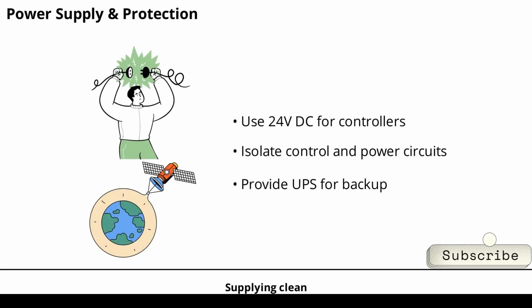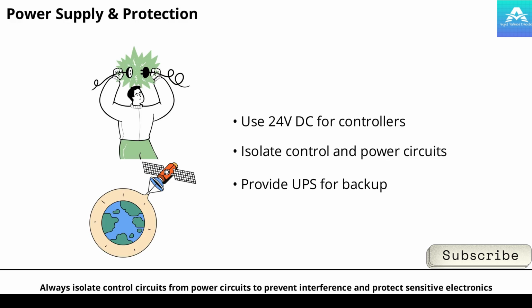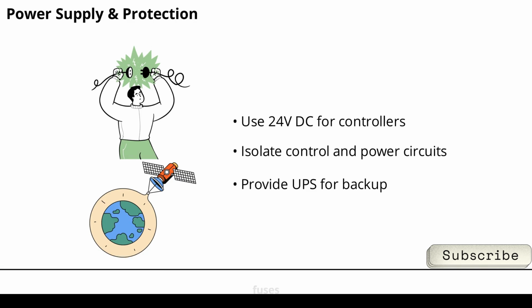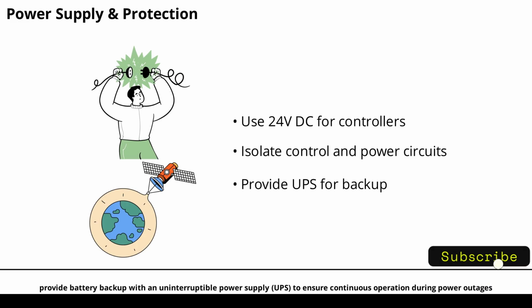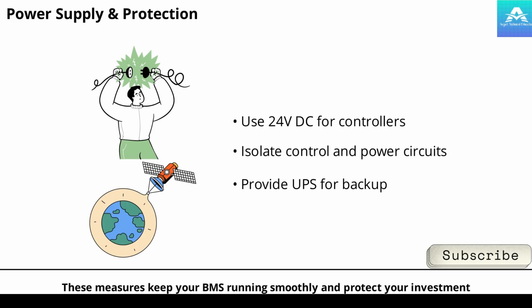Supplying clean, reliable power is vital for DDC panels. Most controllers and I/O modules operate on 24 VDC. Always isolate control circuits from power circuits to prevent interference and protect sensitive electronics. Use MCBs, fuses, and surge arresters to safeguard against overloads and surges. For mission-critical panels, provide battery backup with an uninterruptible power supply, UPS, to ensure continuous operation during power outages. These measures keep your BMS running smoothly and protect your investment.